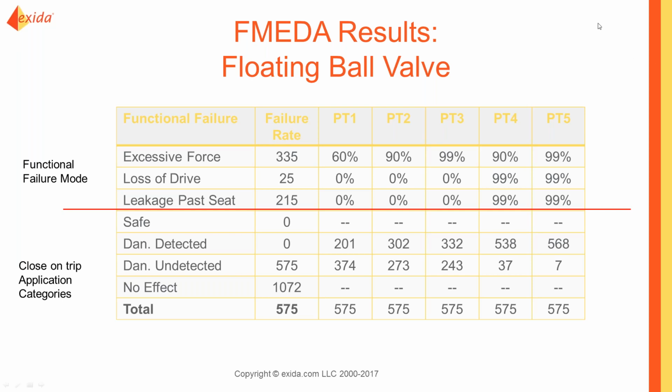It may not be practical to do. So then you might say, well, I might do a different test. Maybe I'll just do a partial valve stroke test. And the standard doesn't say what test you have to do. The standard basically says you need to model it correctly.